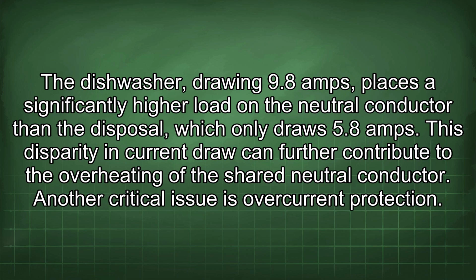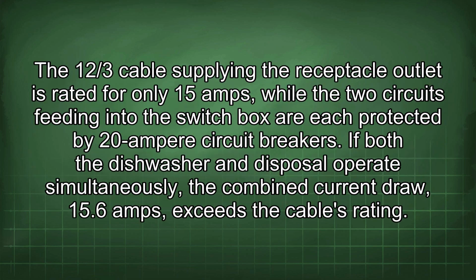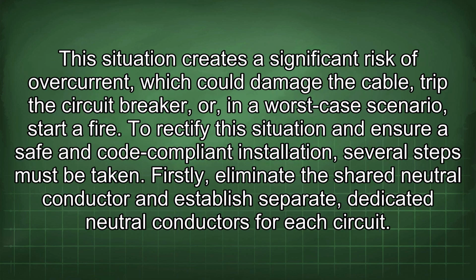Another critical issue is overcurrent protection. A 12/3 cable supplying the receptacle outlet is rated for only 15 amps, while the two circuits feeding into the switch box are each protected by 20 ampere circuit breakers. If both the dishwasher and disposal operate simultaneously, the combined current draw, 15.6 amps, exceeds the cable's rating. This situation creates a significant risk of overcurrent, which could damage the cable, trip the circuit breaker, or, in a worst-case scenario, start a fire.